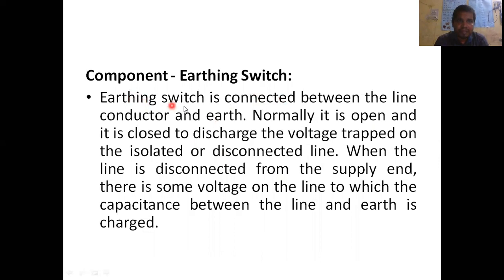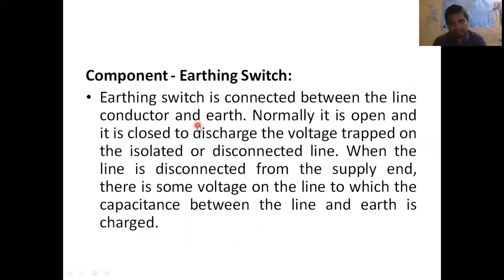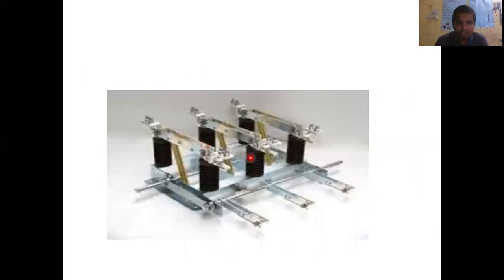Next, the earthing switch. The earthing switch is connected between the line conductor and the earth. Normally it is open, and it is closed to discharge the voltage trapped on an isolated or disconnected line. When you disconnect a line, there may be some trapped voltages that need to be discharged to earth, so you close the earthing switch to discharge to ground.